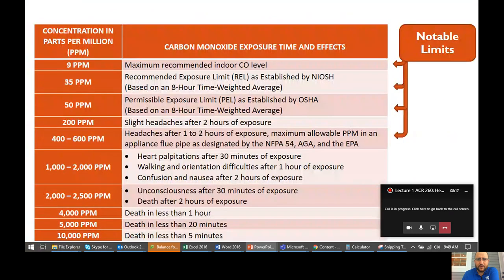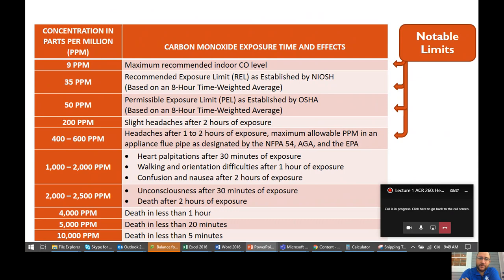Concentration of CO is measured in ppm — parts per million. Ideally you should have zero ppm at all times. Anything above nine ppm is considered something that needs to be addressed. Should be zero, but you could have up to nine; anything ten or above is an indication of an issue. Your meters are going to read this, so if you see anything in the double digits, that should raise a red flag.